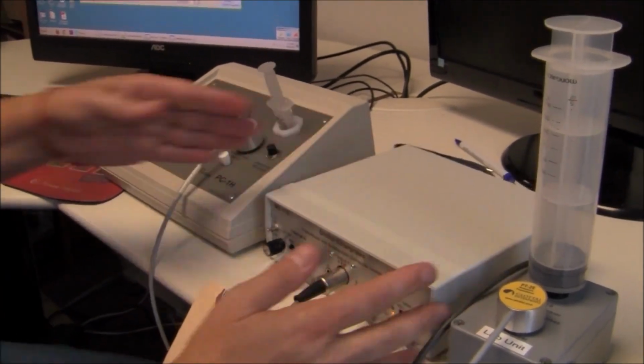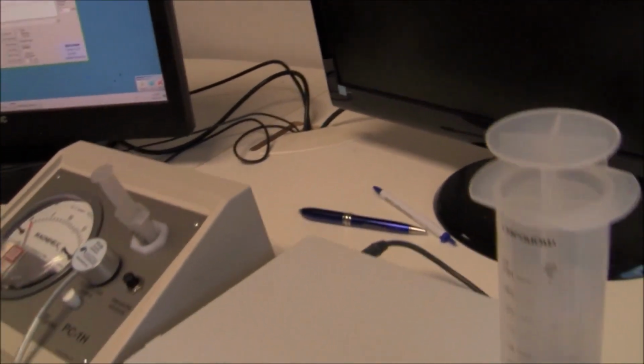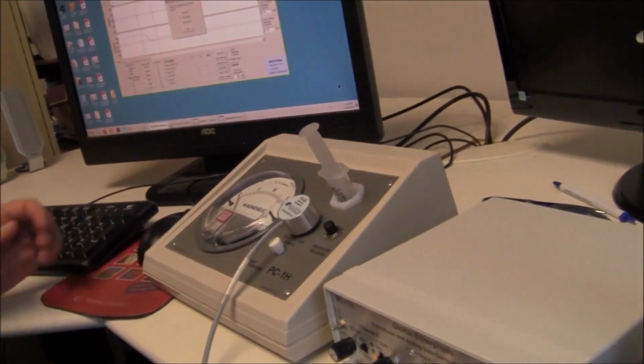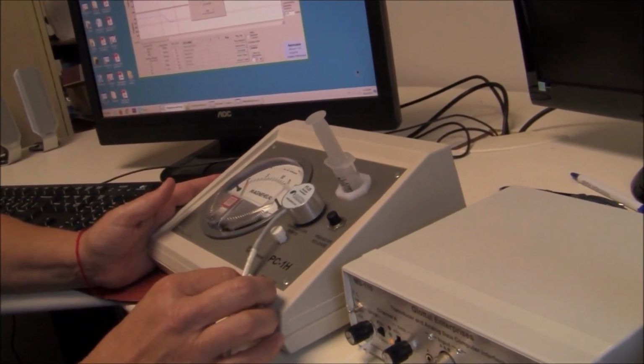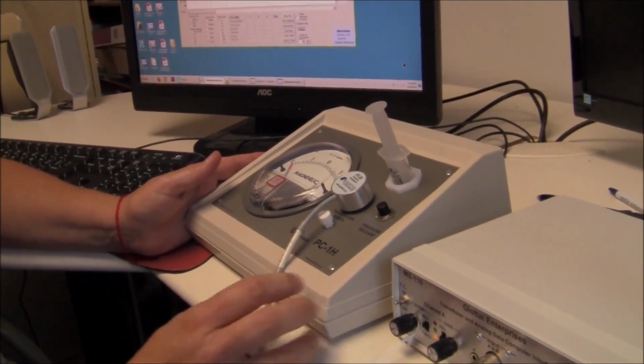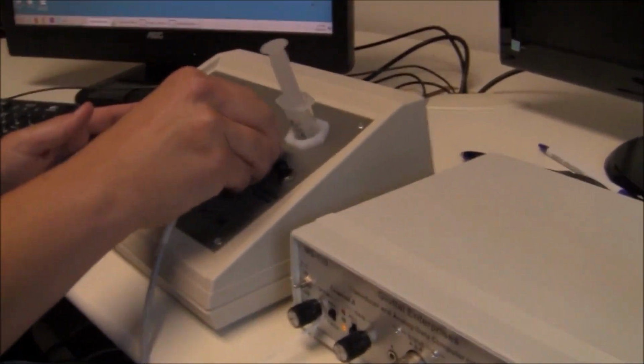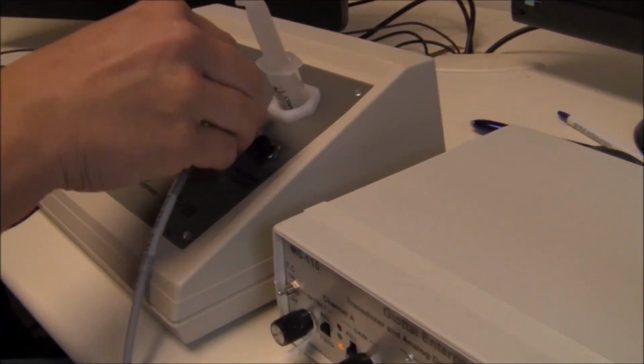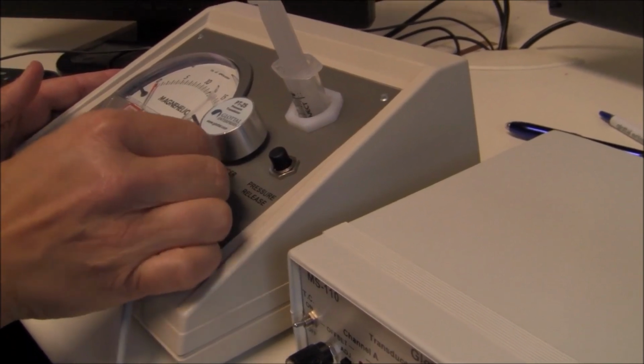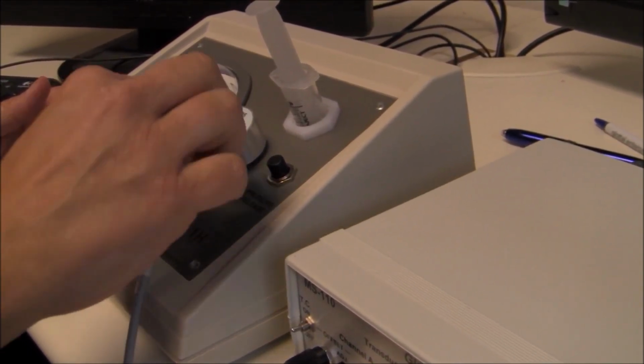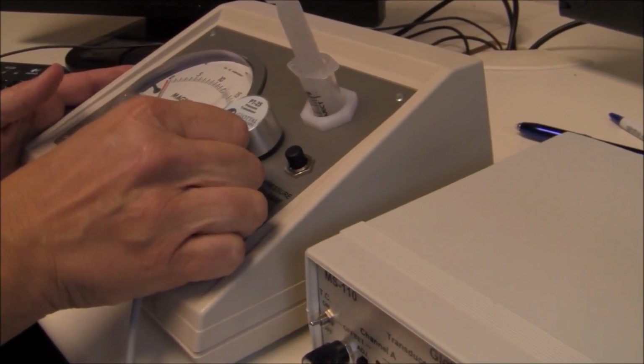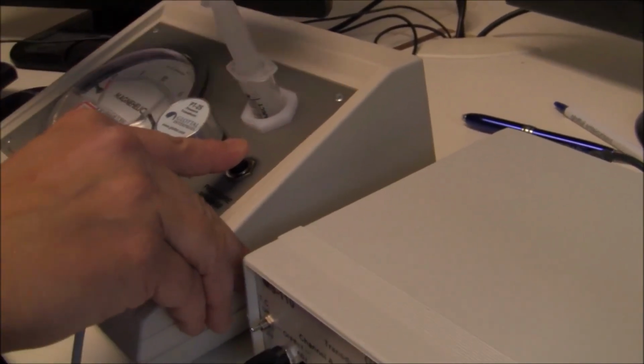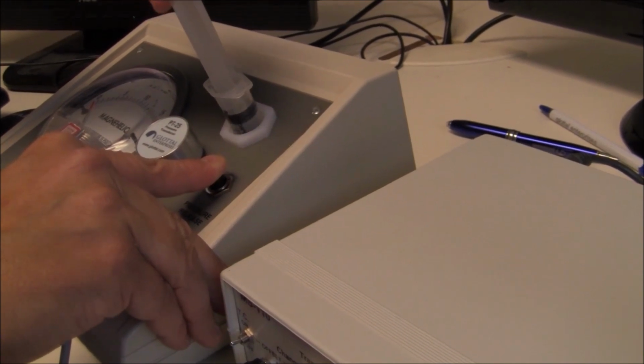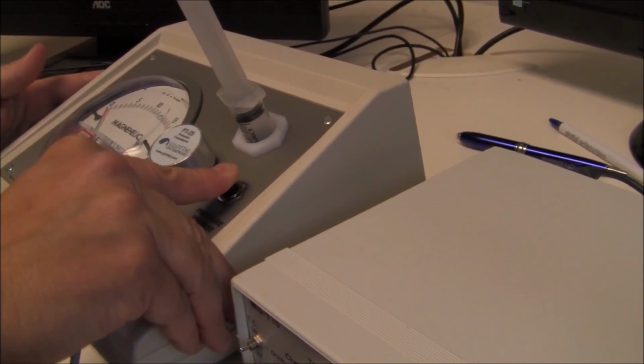Okay, so first we are going to calibrate the pressure transducer, the PT25. So you want to take the PT25 and put it into the transducer port of your calibrator, and make sure that this hole here is closed. Now, to bring the syringe up, you always want to press the pressure relief valve first, so you're not putting a negative pressure onto the transducer, which could damage it.